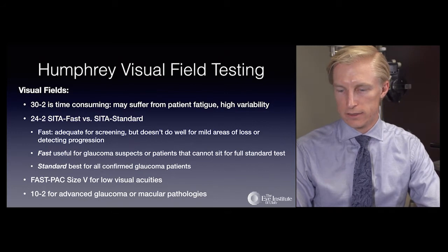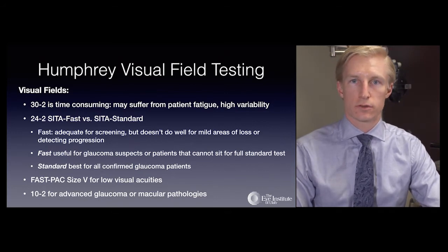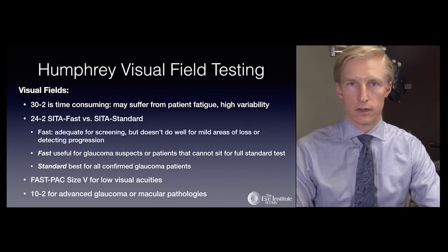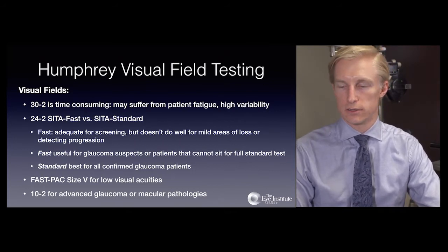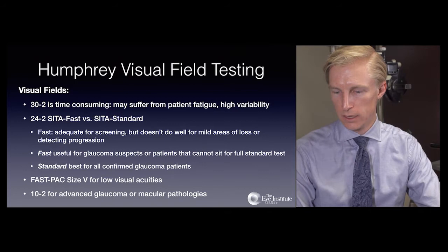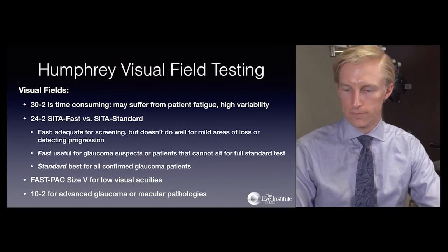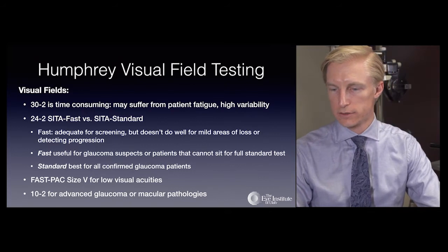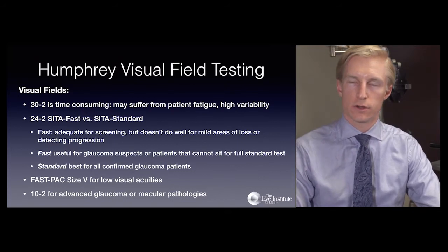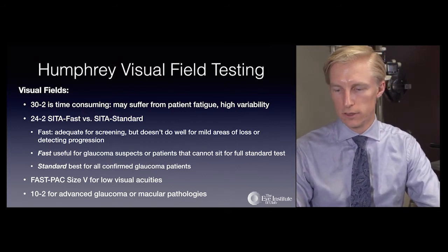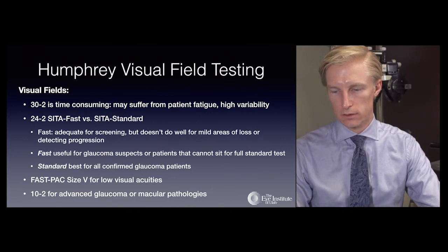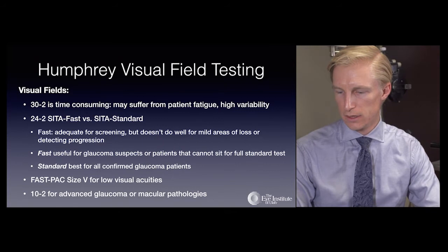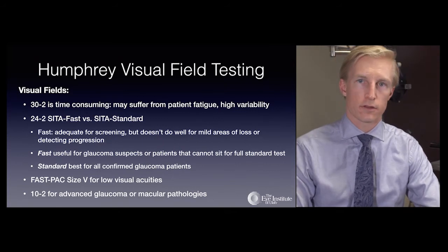The FAST-PAC size 5 is available for patients with low visual acuity, providing a larger stimulus while still allowing detection of scotomas due to glaucoma. The 10-2 algorithm is useful in advanced glaucoma when peripheral vision is sufficiently changed that a wider field provides insufficient detail, and is also useful for macular pathologies.